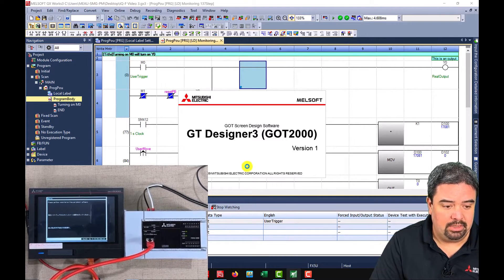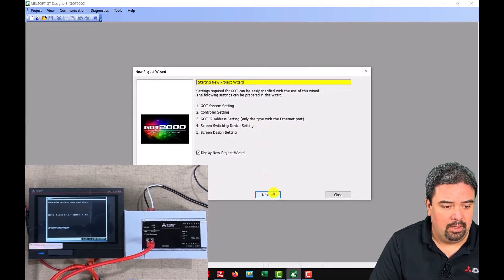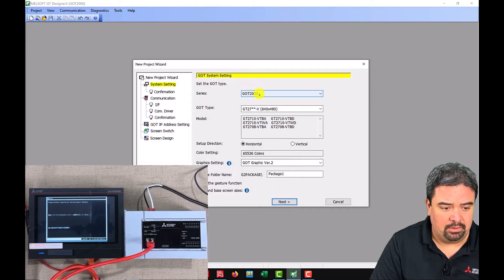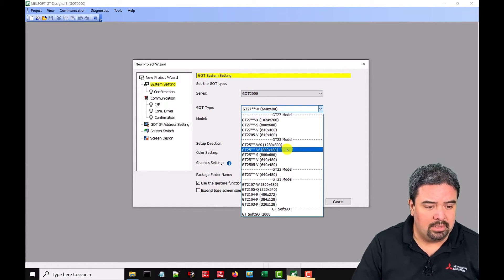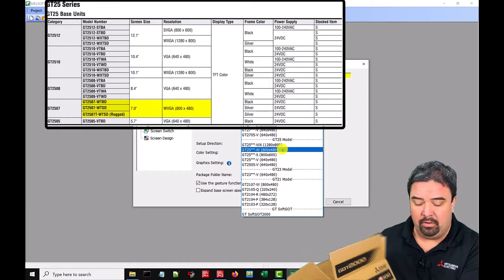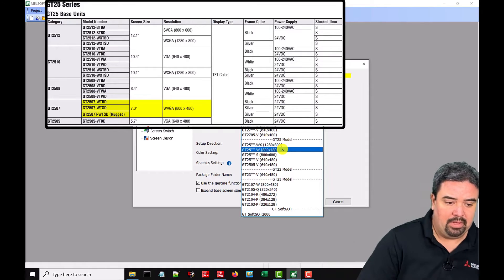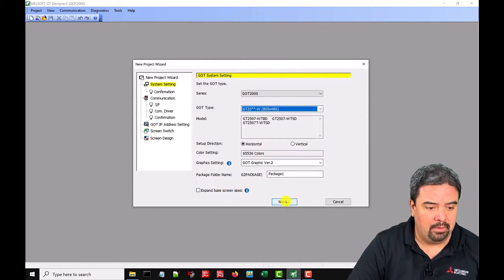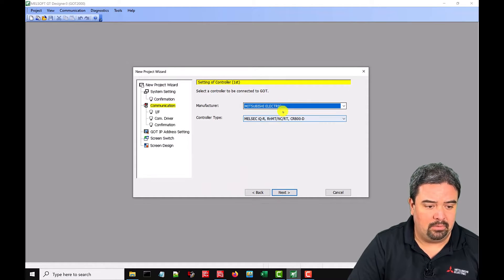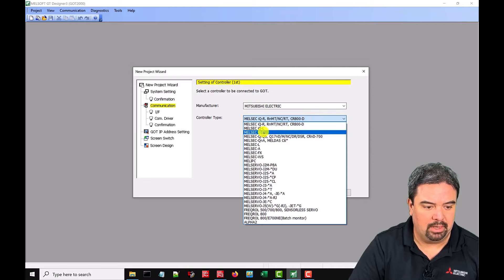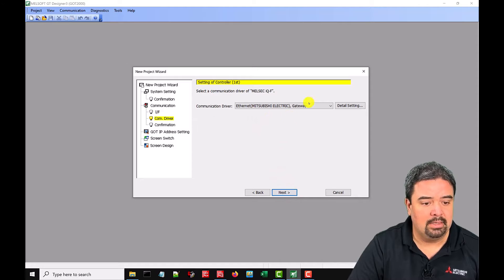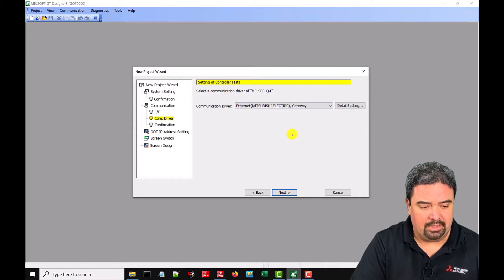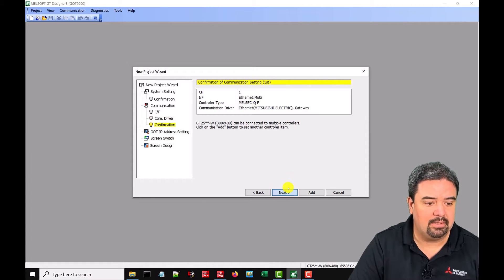First thing we do is we open GT Designer 3. We start a new project. We have a nice wizard here that we can work through so we want the GOT 2000. We're going to select the GT25 series. In our case we have the GT2507W so the W will tell us what type of resolution we have. We just say next, next. Now we have to tell it what type of PLC we're talking to. So we're talking to an IQF PLC. We say next, over Ethernet, yes. It's going to set up the Ethernet as a gateway. That's just the driver that it needs to install. We say yes.